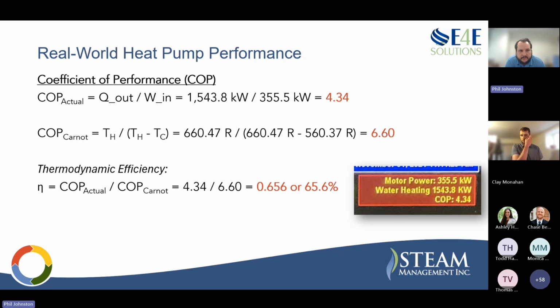In this real life scenario, we can also look at the COP, and you can see that the work in real time from the motor, which is driving the compressor and pressurizing that gas, is around 350 kW, and the heat rejection is significantly higher than that. It's around 1500 kW. So that roughly comes out to a COP of 4. If we look at this from just a pure temperature standpoint, it is higher. So the rules that Clay laid out in the beginning play out here in real life, and we have a thermodynamic efficiency of around 65%. Now, that is a bit higher than what Clay had, and what I'd comment on that is this is an ammonia heat pump.